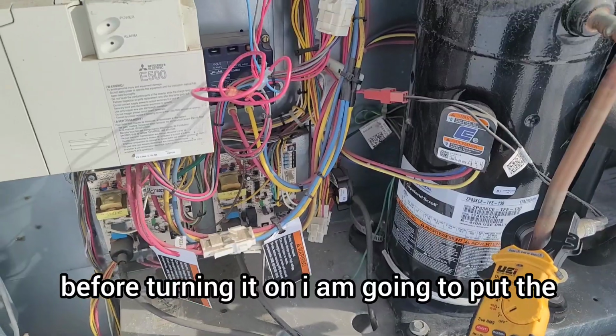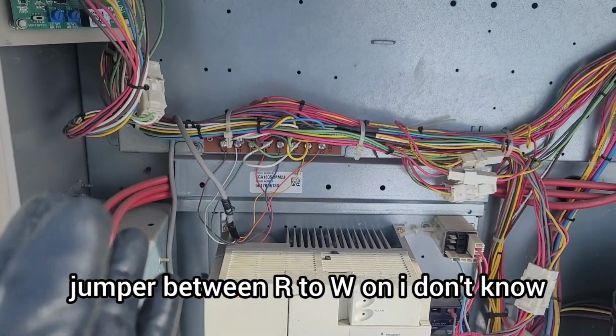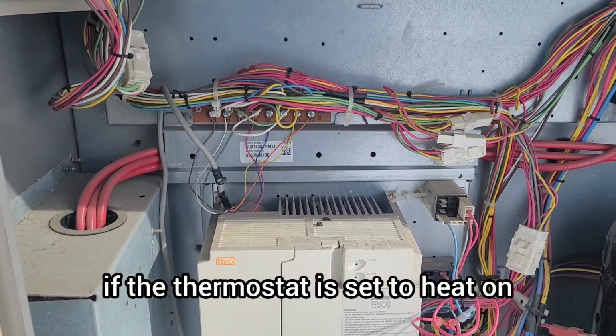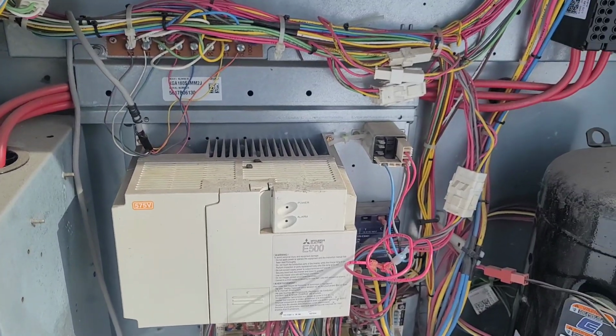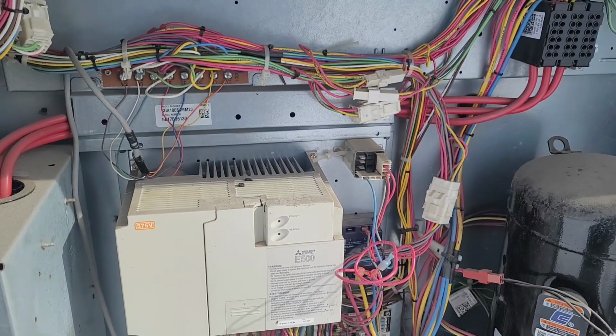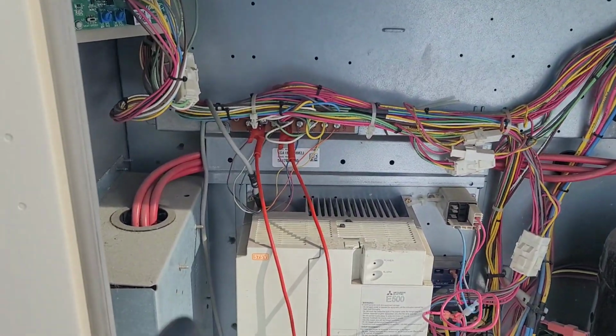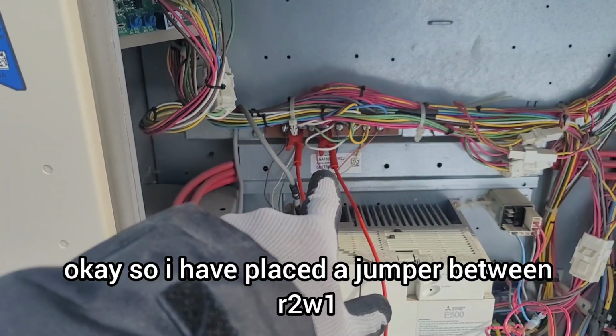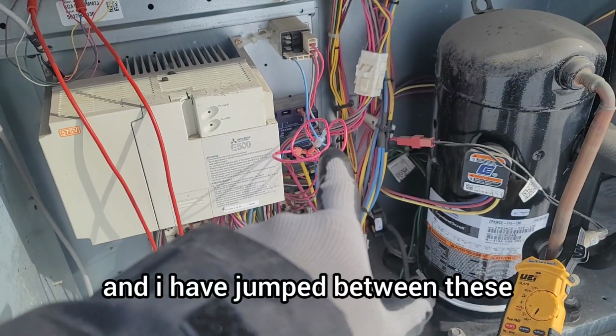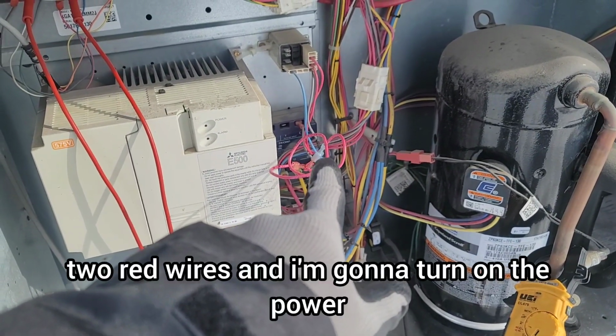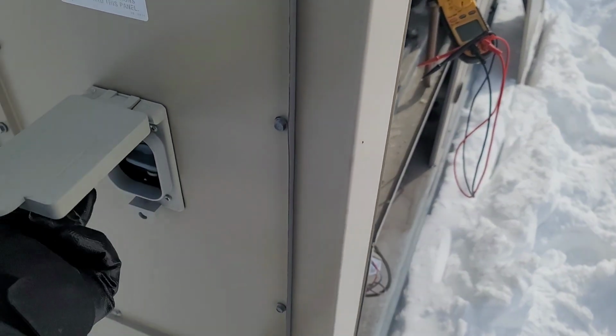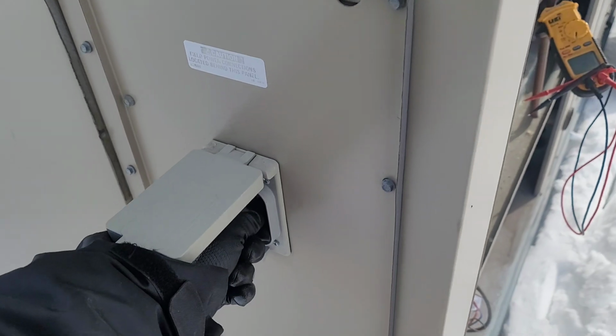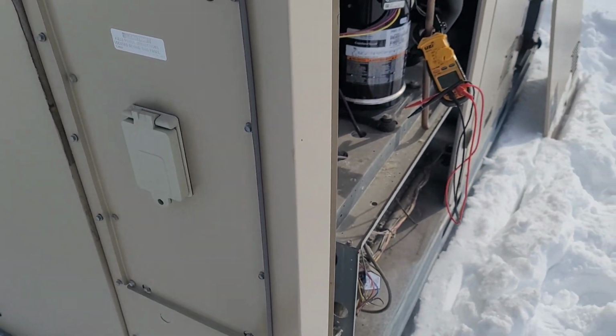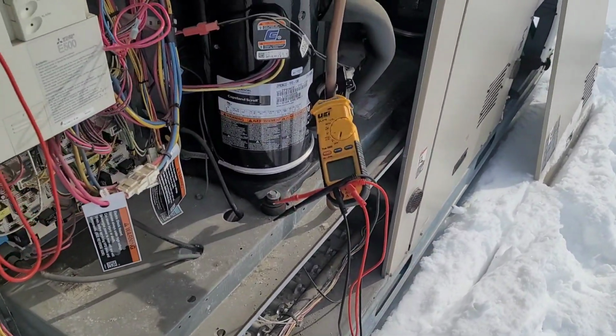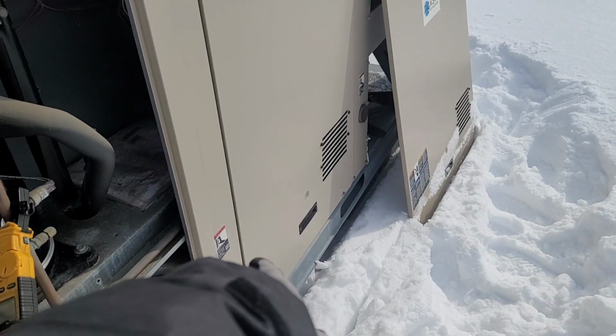So I have jumped between these two red wires, and now I'm gonna turn on the power. Before turning it on, I'm gonna put a jumper between R to W1. I don't know if the thermostat is set to heat or not. Let's do it. Okay, so I have placed a jumper between R to W1, and I have jumped between these two red wires, and I'm gonna turn on the power. Hopefully everything is gonna be okay, and we will have, oh yeah, the inducer motor started.